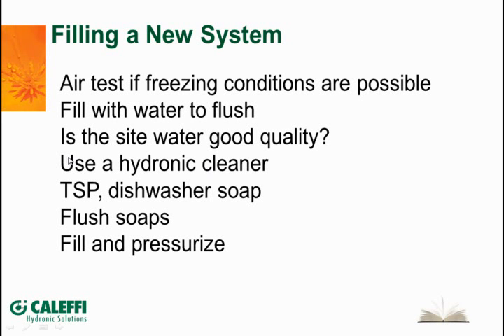I'm a big fan of using some sort of hydronic cleaner on these new boilers and new systems that we put in, just because I know there are oils and assembly lubes and different contaminants in there. There's dirt and debris in your black steel pipe and different pipes. So there are a lot of companies that have these hydronic cleaners that you typically put in and run for a couple hours or maybe overnight, and then flush them out. They condition everything in the system.